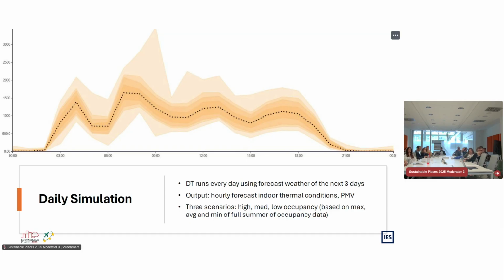What we've set up is a cloud simulation of the digital twin running every day, taking the forecast weather conditions and outputting, at an hourly level, the indoor thermal conditions, calculating the PMV for that space. We do this for 3 scenarios extracted from this data: worst case of highest occupancy, average occupancy, and lowest occupancy.